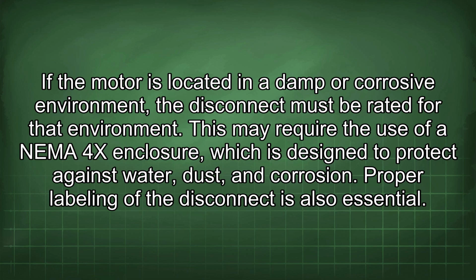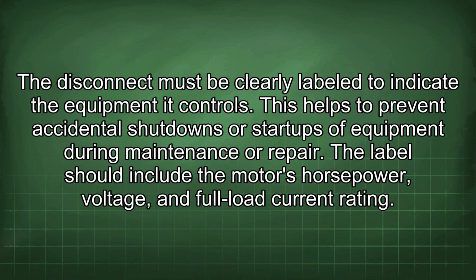Proper labeling of the disconnect is also essential. The disconnect must be clearly labeled to indicate the equipment it controls. This helps to prevent accidental shutdowns or startups of equipment during maintenance or repair. The label should include the motor's horsepower, voltage, and full load current rating.